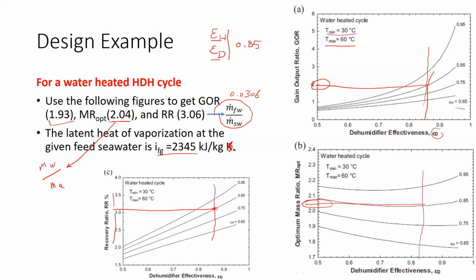In real life, what we do is go through iteration, because you need to build a unit. In order to build a unit, you need to come up with an estimate. You don't know the size, you don't really know the conditions. So you go through an estimate, and then you iterate until you reach the size of the system, or you make assumptions like that. You say, I'm going to plan for an effectiveness of maybe 70 or 75%, and then you build the system and keep trying. This is if you want to go ahead and build it on the ground.